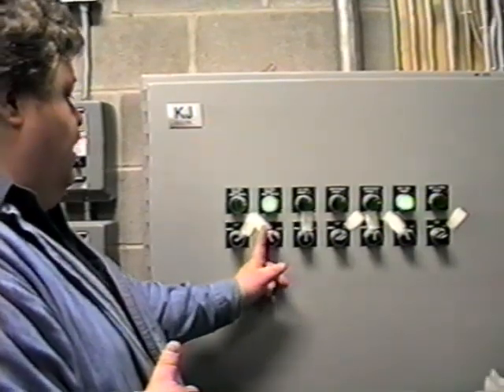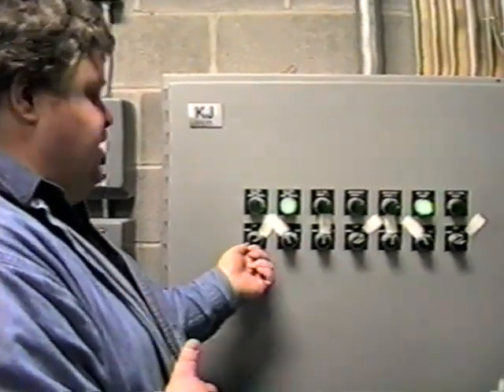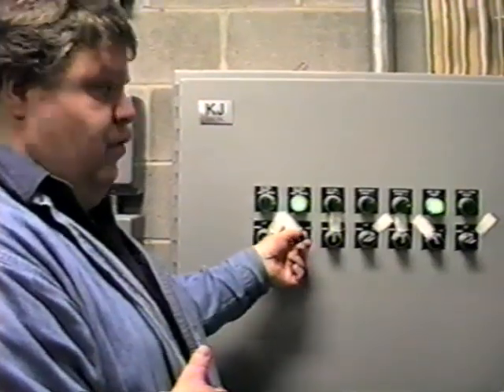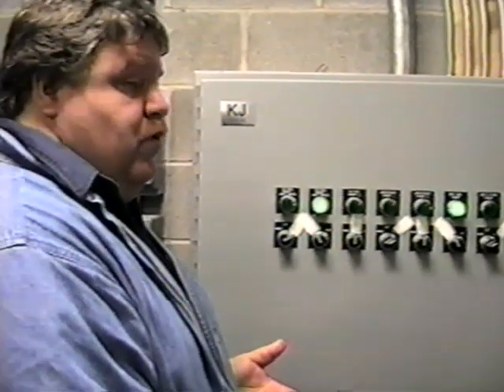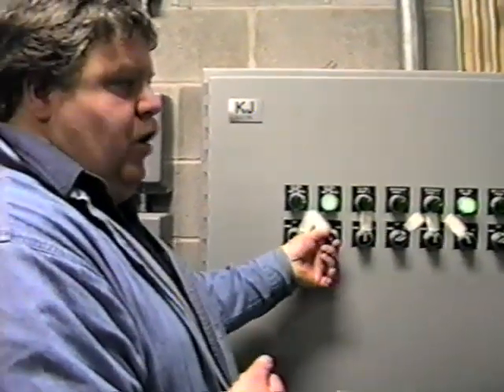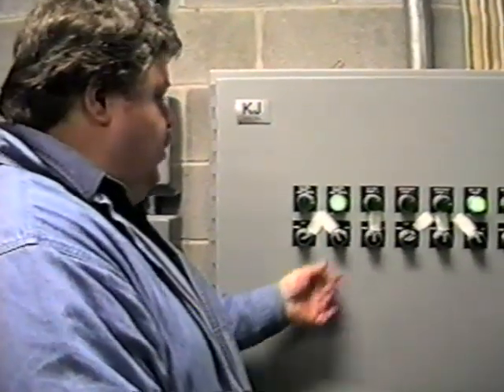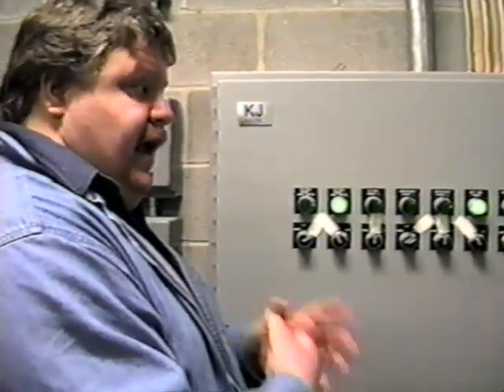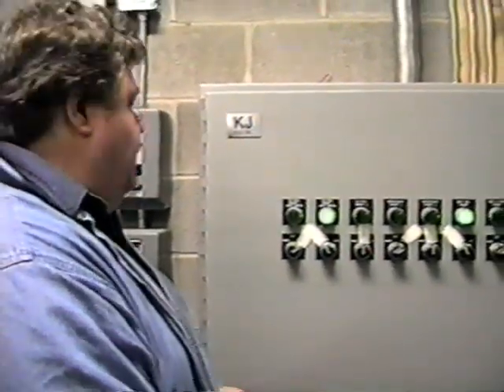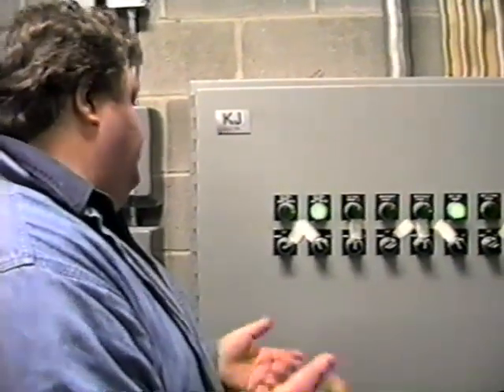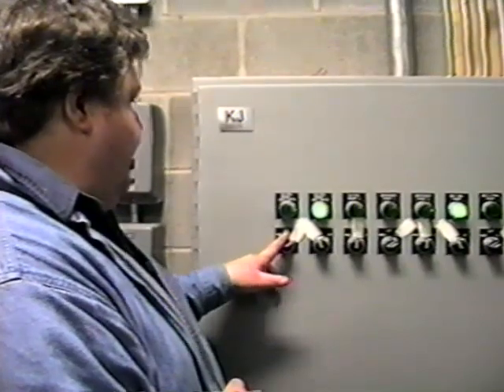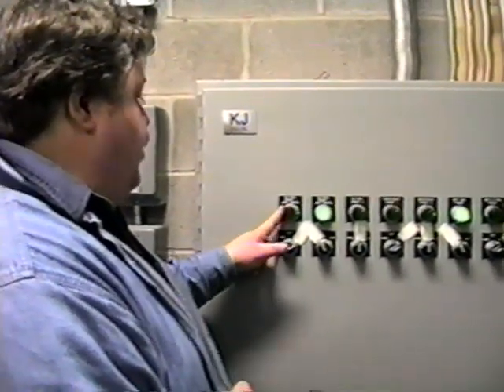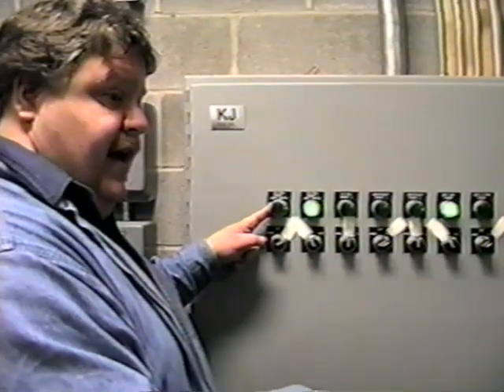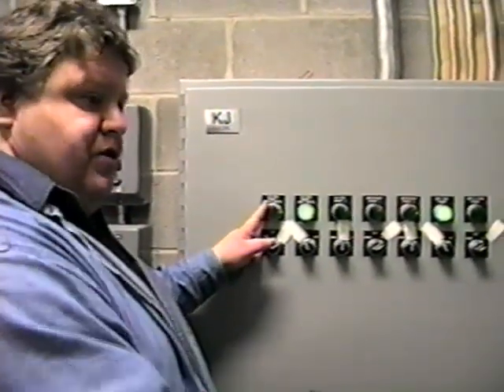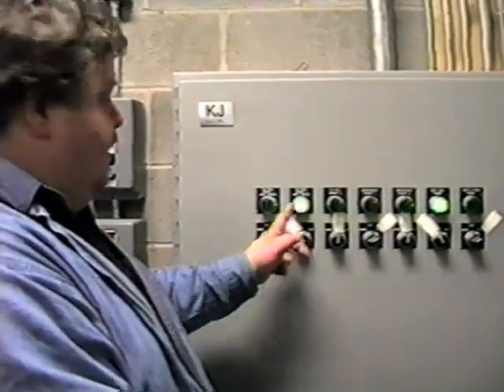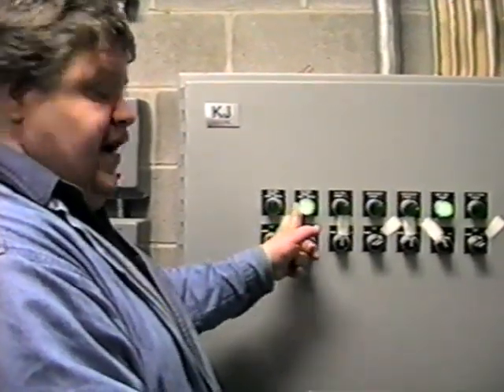This switch basically is, if I'm in hand position, I can pick high or low. Normally it would be the high position because you want it to chill. You could do it in the off season. Let's say you're going to thaw the floor out, you could throw it to low, and it'll generate a little bit of heat into the brine and help you thaw out. But normally this will be automatic. This will light up when your ice temperature is satisfied, so you're cold enough. This pump will switch to low speed, so this will come on and this will be off. Right now we're calling for cooling, so this one's on.